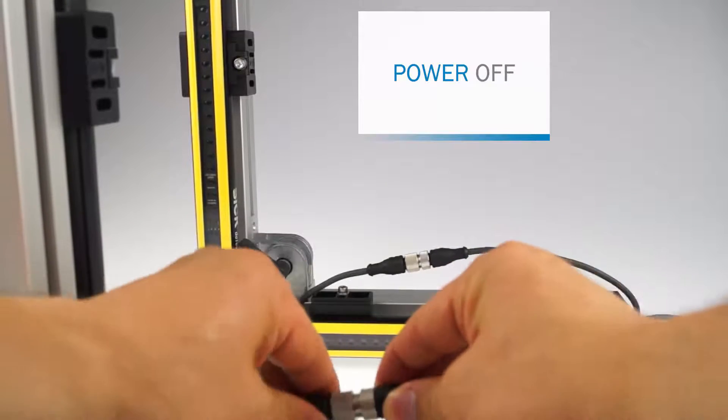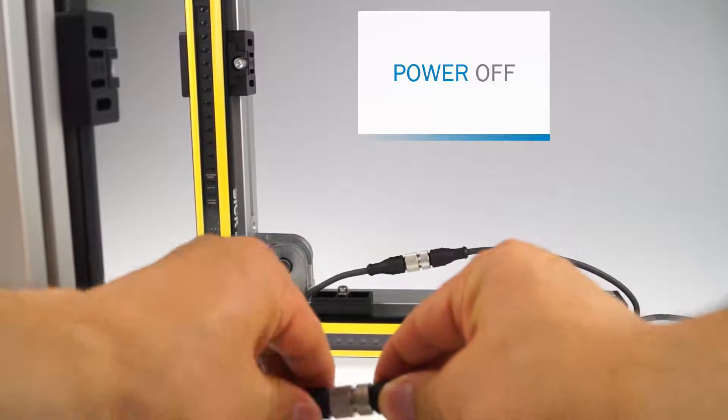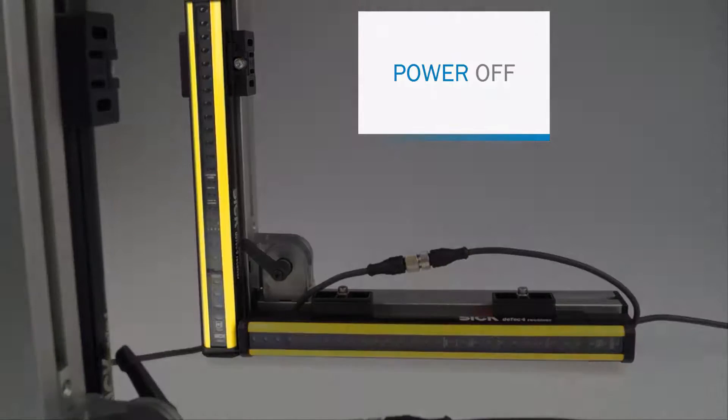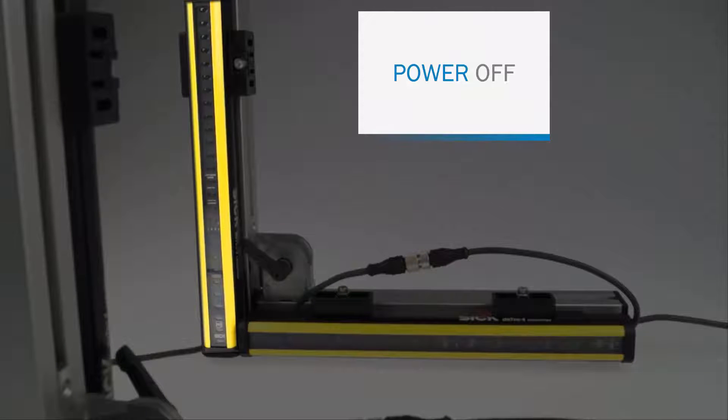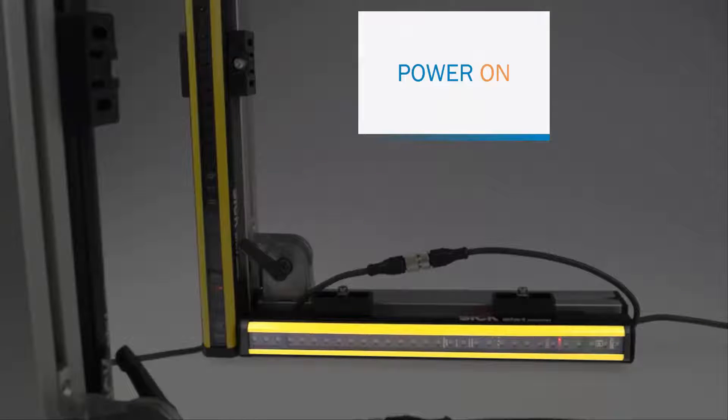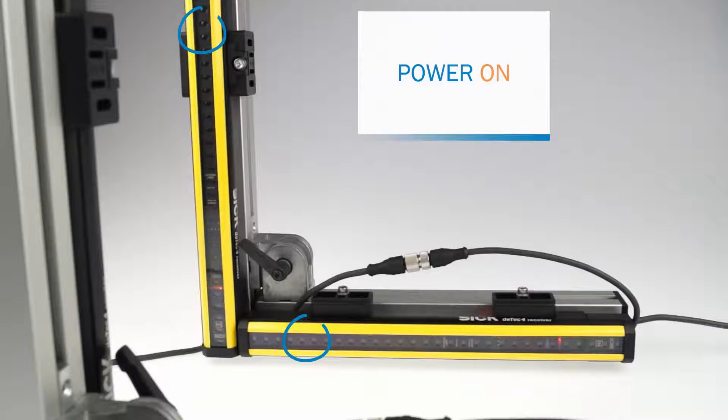If everything is wired correctly, you can connect the system with the power supply again. The devices which are connected directly to the power supply represent the host devices, while all other devices are guest devices. Now, the field LEDs of the devices are flashing green. This is the sign that the devices have entered the configuration mode and the cascading has been successful.